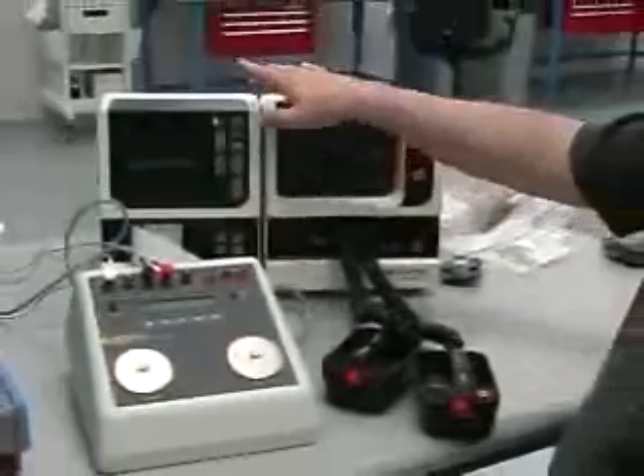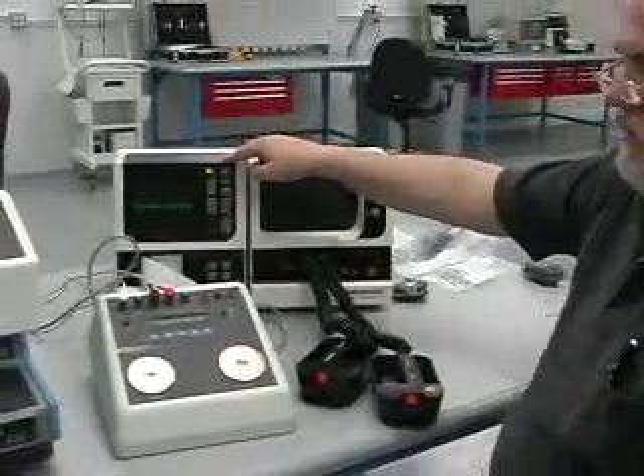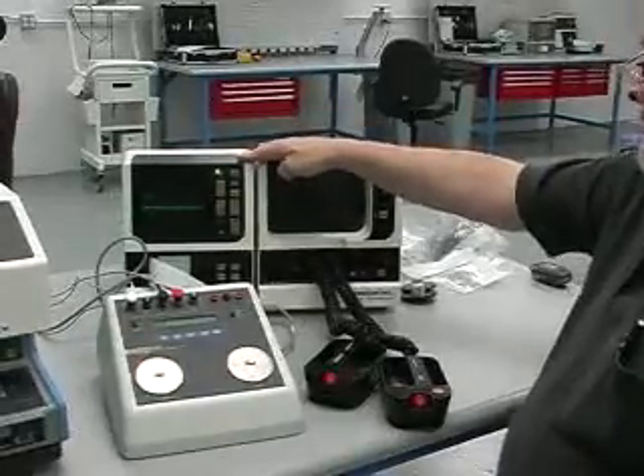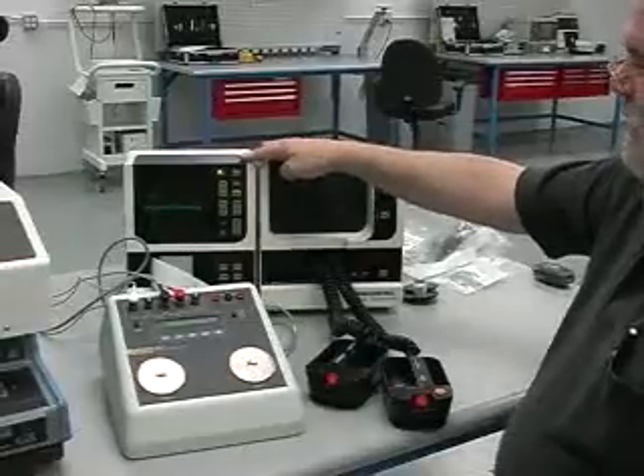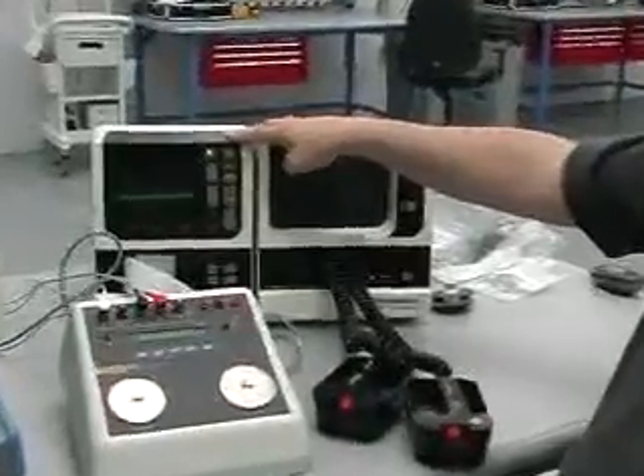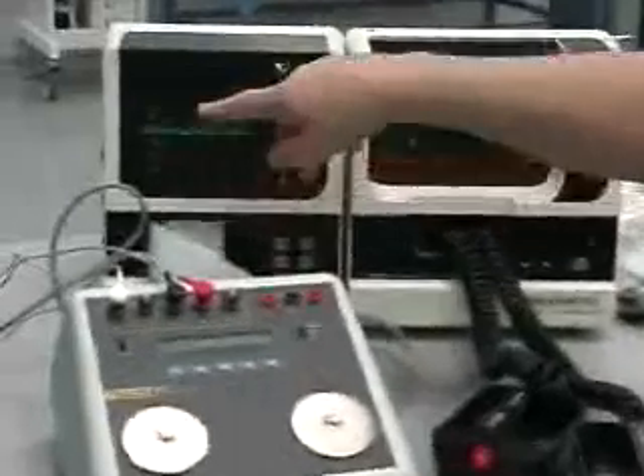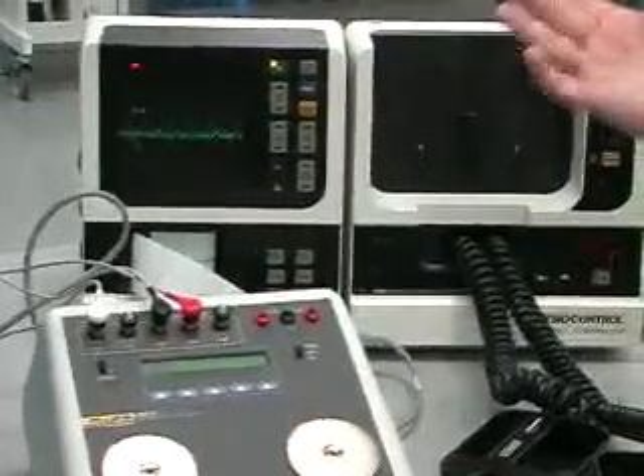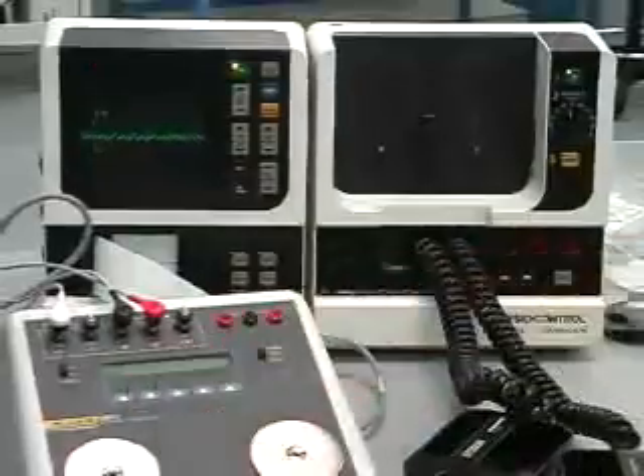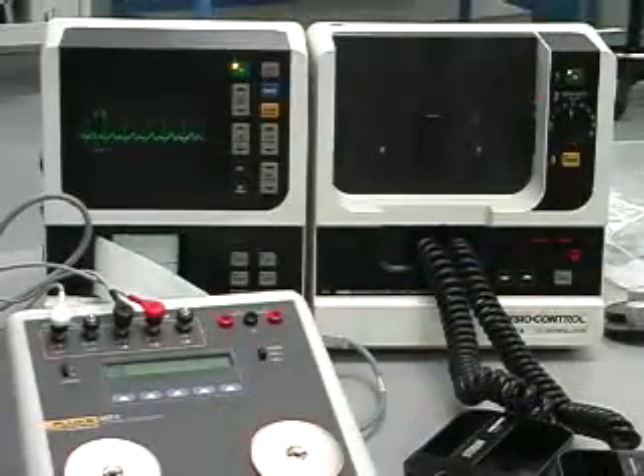With the monitor, you get a little bit of an exaggeration of that because the low end frequency response of these things by design isn't that good, because you don't need DC response, since muscle tremor and other noise would just give you more artifact. With that poor low frequency response, you don't get the resolution on the low frequency. So you will see a little bit more of a pulse in that second lobe, but to get a good measurement of it, you could go to a direct DC-coupled scope to look at it, or just simply look at the over reading here, and that will tell you what the component is of that second lobe or negative lobe.